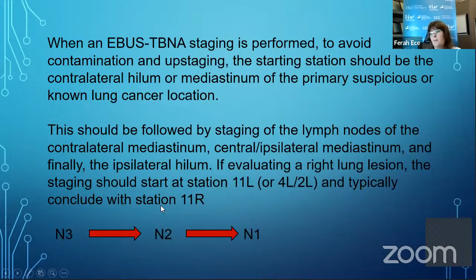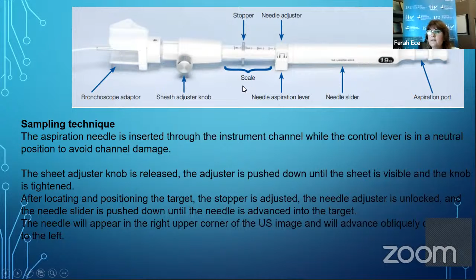Okay, sampling technique is a complicated one, really complicated. First, the aspiration needle, the EBUS needle, is inserted through the instrument channel. But while doing this, you have to be in neutral position. Otherwise, you can damage the channel of the bronchoscope. When you lock the bronchoscope adapter to the bronchoscope, the sheath adjuster knob is released and the adjuster is pushed down until the sheath is visible, like here. You see the sheath first.